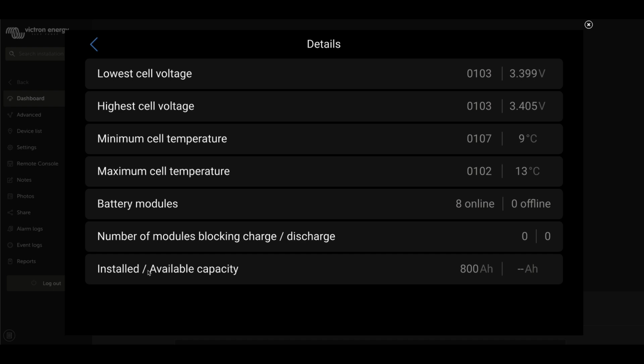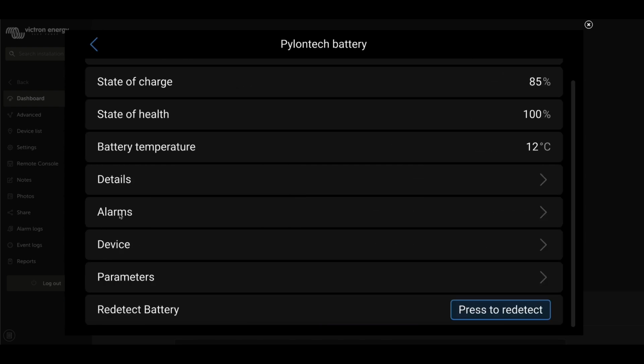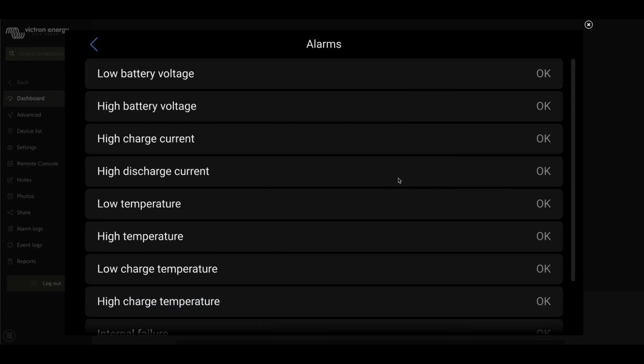The available capacity will start to change if a cell is offline or blocked, or for some other reason something has shut down there. Let's look at the alarms page. This one is going to be your most obvious, hey, something's wrong, what's going on? Low, high battery voltage: obviously, if the battery gets too drained, you get a low battery voltage alarm, and a high voltage alarm if it's too full.